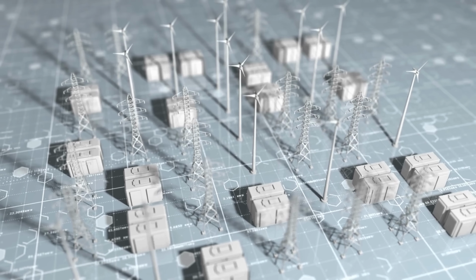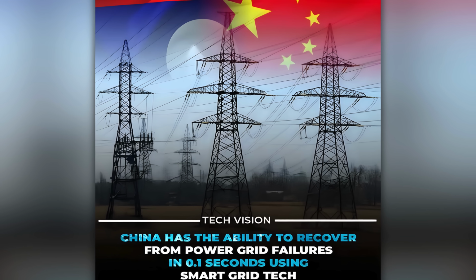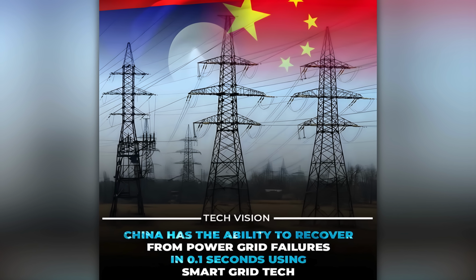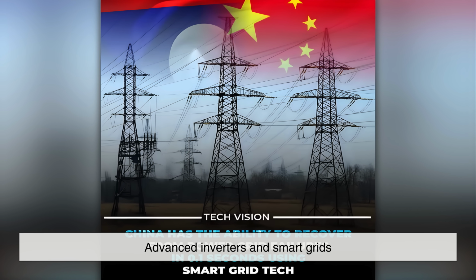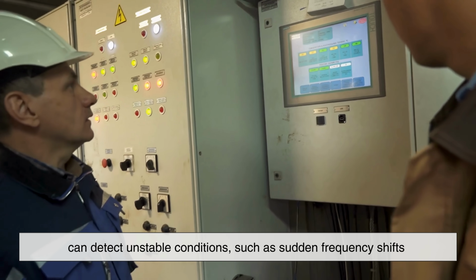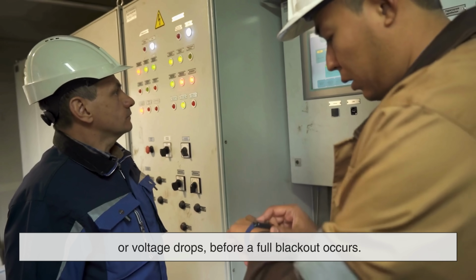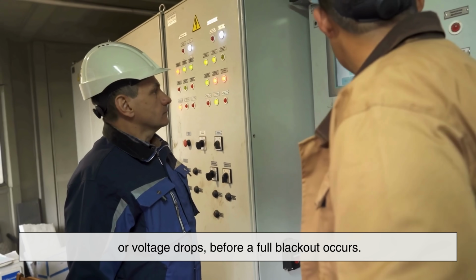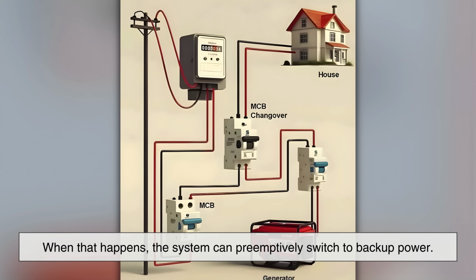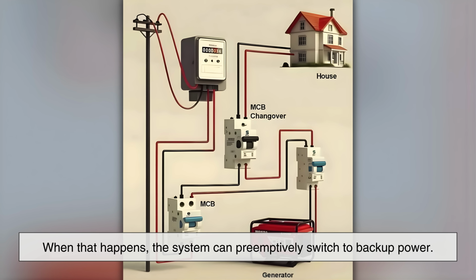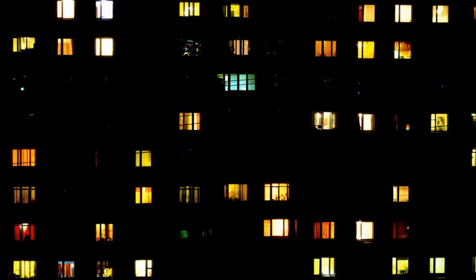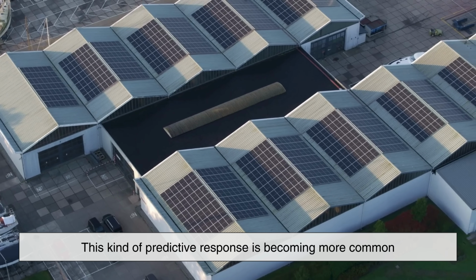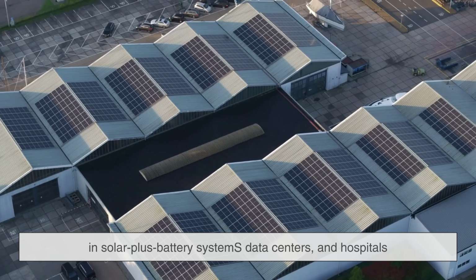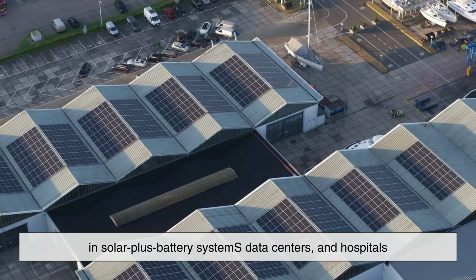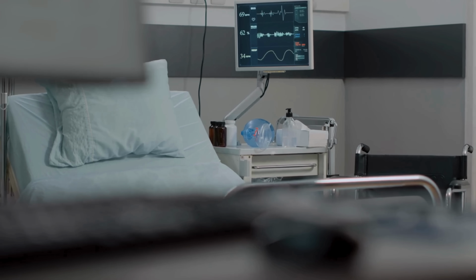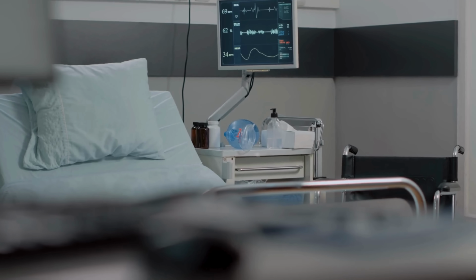Modern backup systems are getting even smarter. Some don't just react to outages, they anticipate them. Advanced inverters and smart grids can detect unstable conditions, such as sudden frequency shifts or voltage drops, before a full blackout occurs. When that happens, the system can preemptively switch to backup power. To the user, there's no outage at all. This kind of predictive response is becoming more common in solar-plus-battery systems, data centers, and hospitals, where even a momentary loss of power is unacceptable.